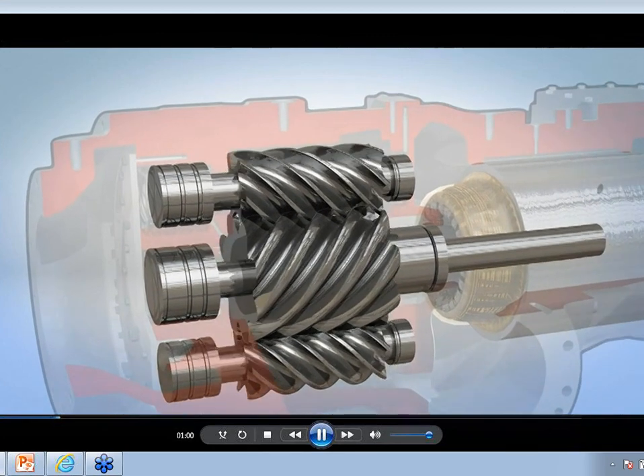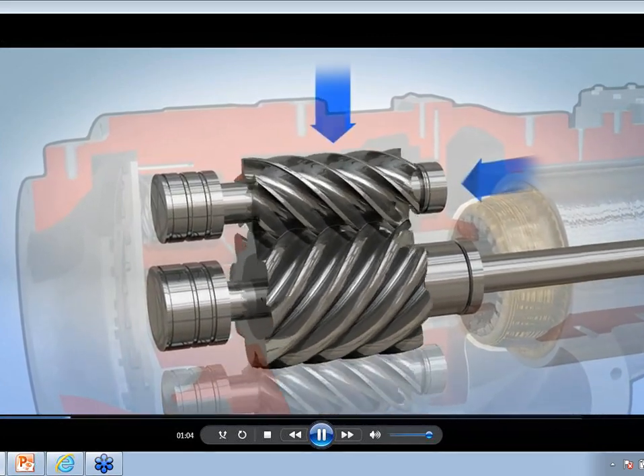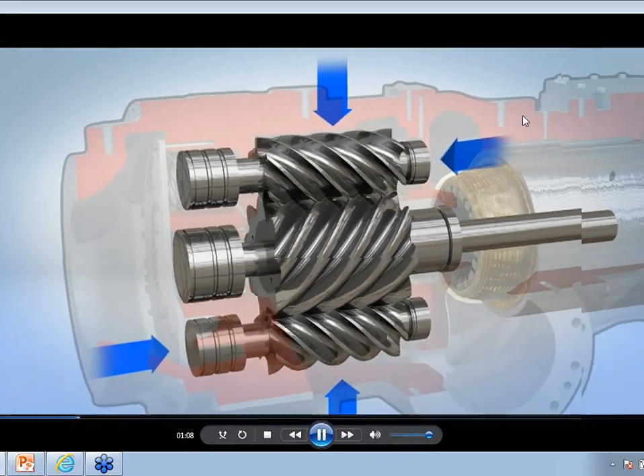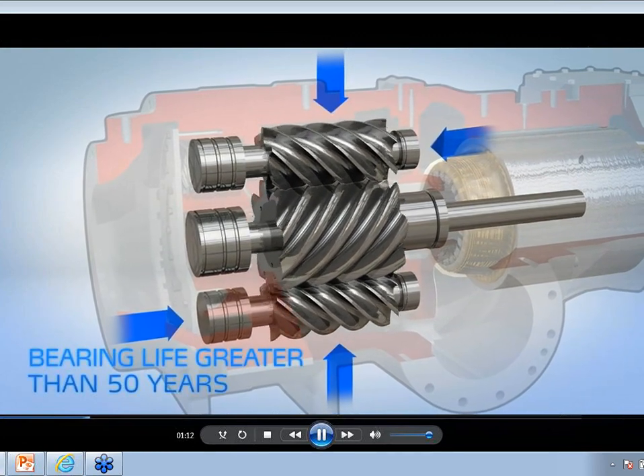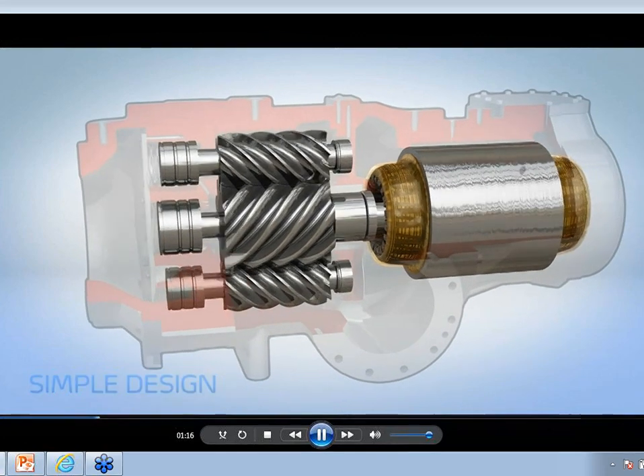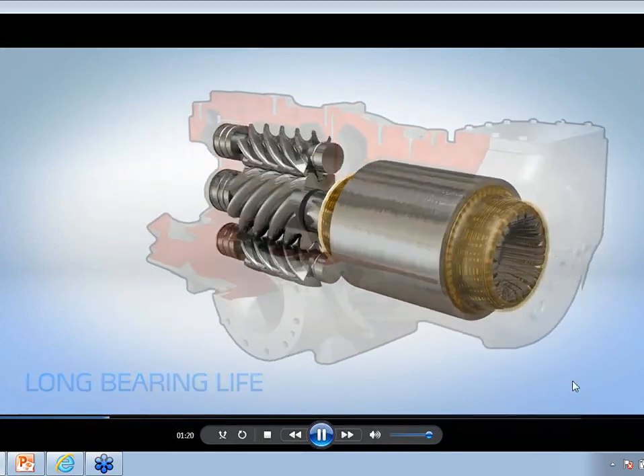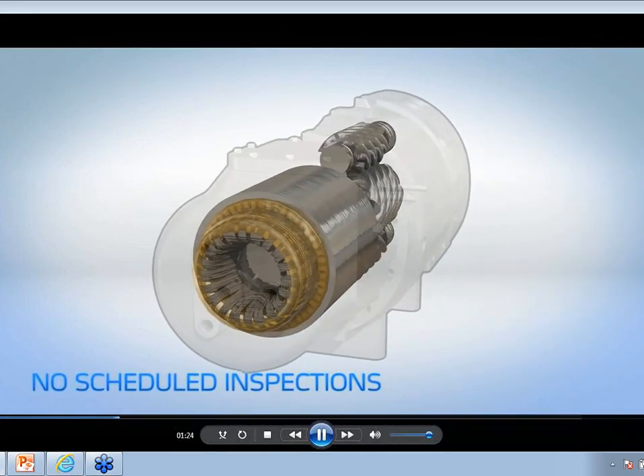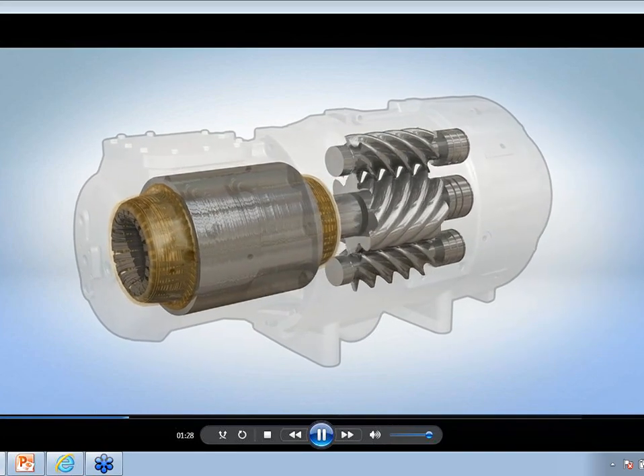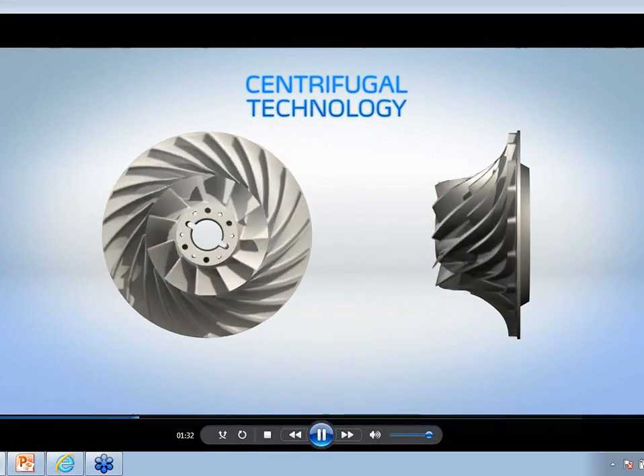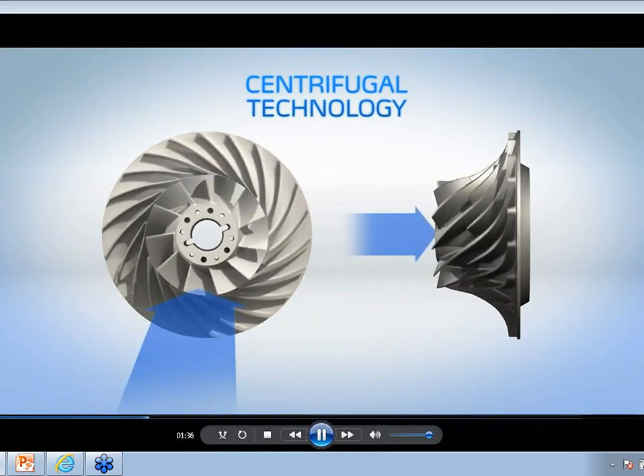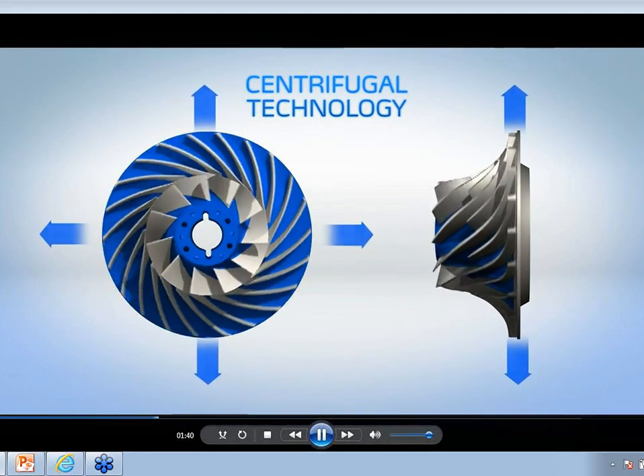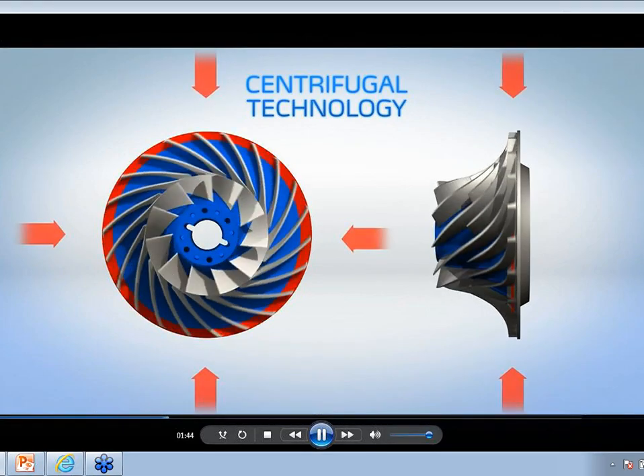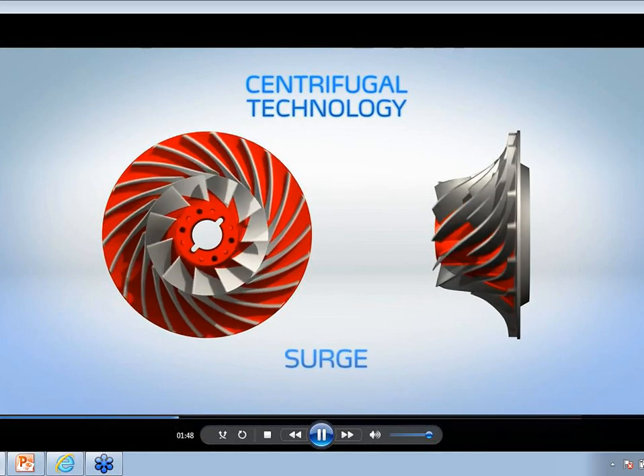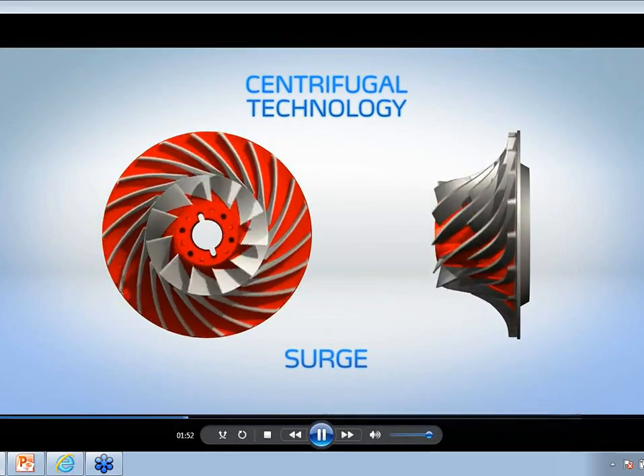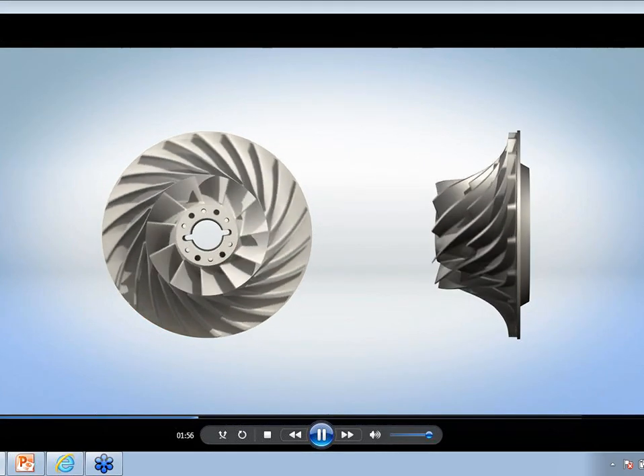Conventional twin-screw compressors experience unbalanced load forces, but the innovative tri-rotor design ensures cancellation of axial and radial loads so effectively that at ASHRAE conditions, the lowest bearing life in the compressor is over 50 years. The simple and direct design, low component count, and long bearing life mean there is no scheduled compressor teardown or inspection required. But it's the fundamental difference in the 23XRV's compression process that delivers a crucial advantage over centrifugal technology. Centrifugal compressors rely on tangential velocity to move refrigerant gas through an open path between the evaporator and condenser. If the compressor cannot generate enough force, the gas will flow in reverse, a phenomenon known as surge, and the chiller may shut down. Unlike centrifugal compressors, 23XRV compressors have no open path and no potential for surge.